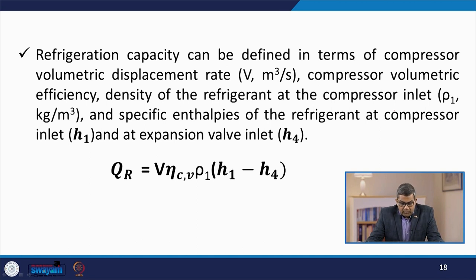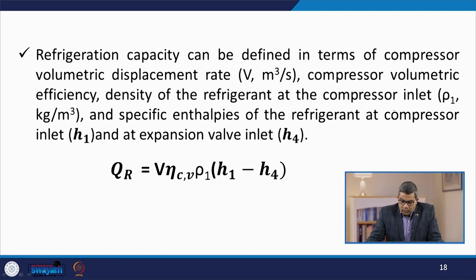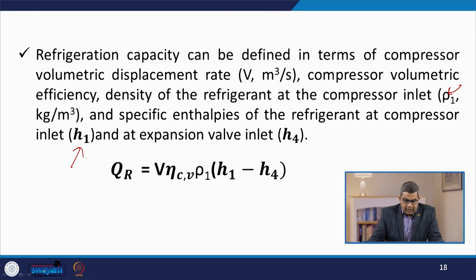Refrigeration capacity can be defined in terms of: compressor volume displacement rate V (m³/s), compressor volumetric efficiency η_cv, density of refrigerant at compressor inlet ρ₁ (kg/m³), and specific enthalpies of refrigerant at compressor inlet h₁ and at expansion device inlet h₄. The formula is: Q_R = V × η_cv × ρ₁ × (h₁ − h₄).